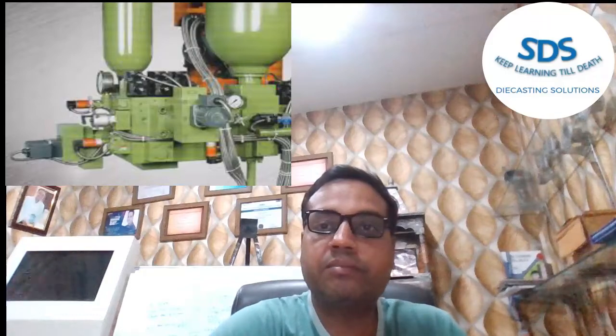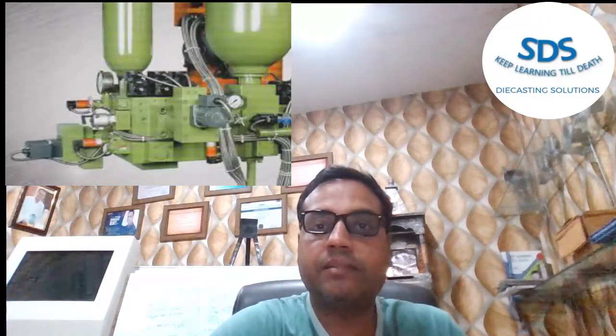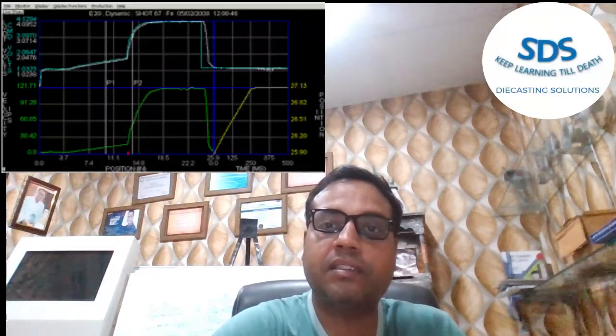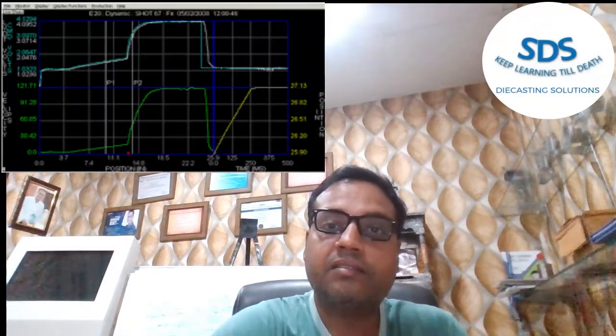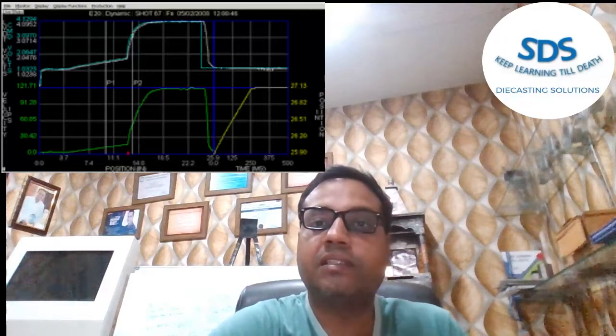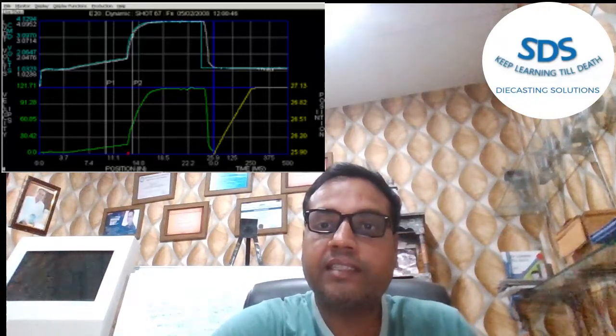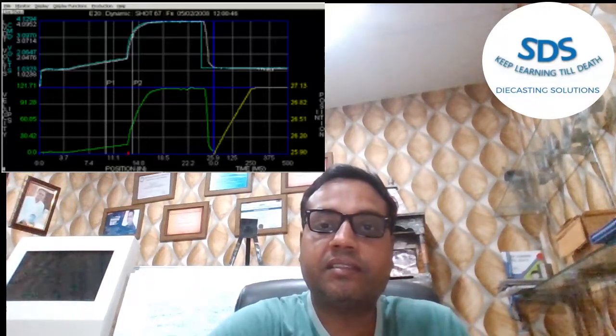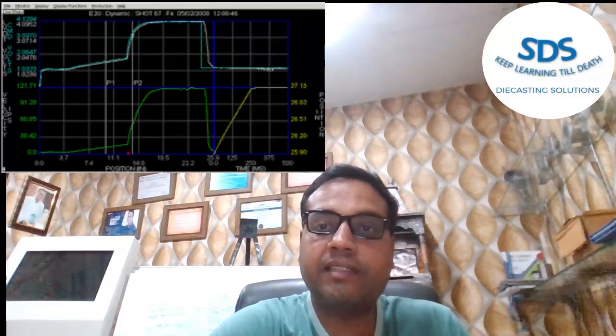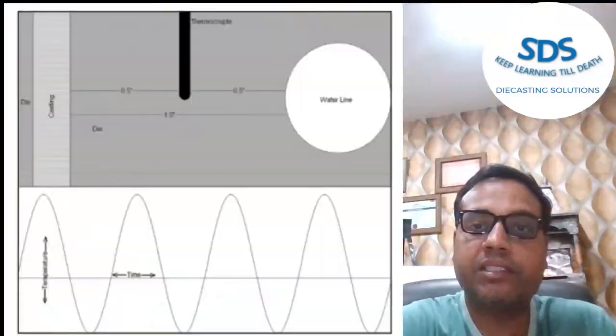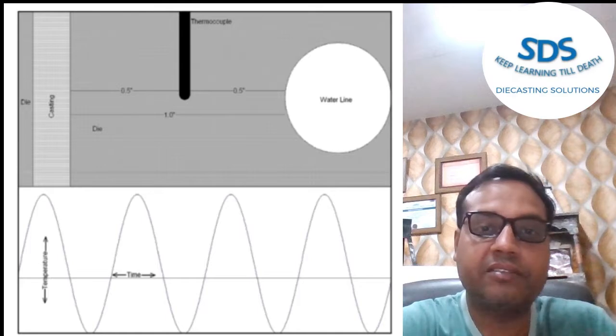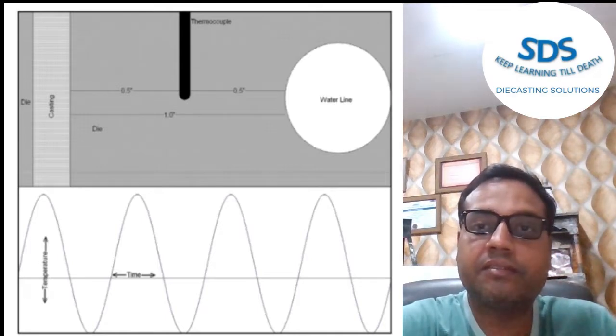Closed loop control systems require direct control at the measurement point. Thermal closed loop control is not effective because the thermocouple must be some distance away from the heat source in the case of die temperature. If closed loop control is applied, the die temperature will oscillate, as you can see in this figure.